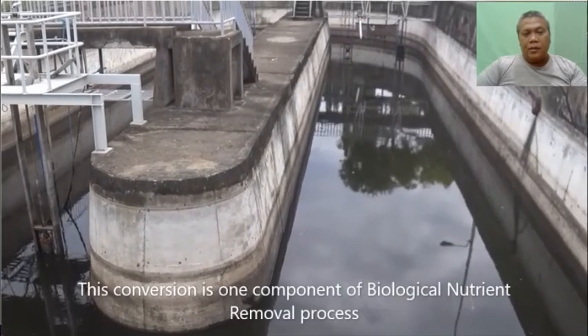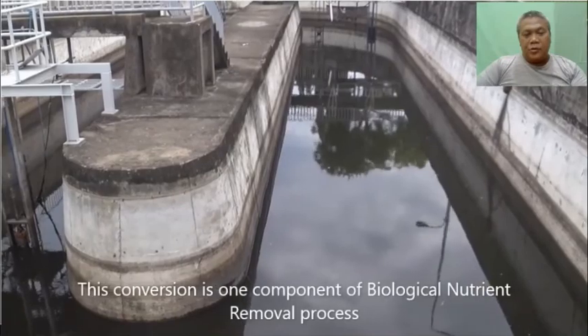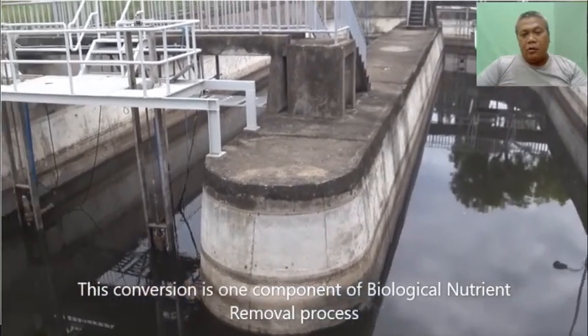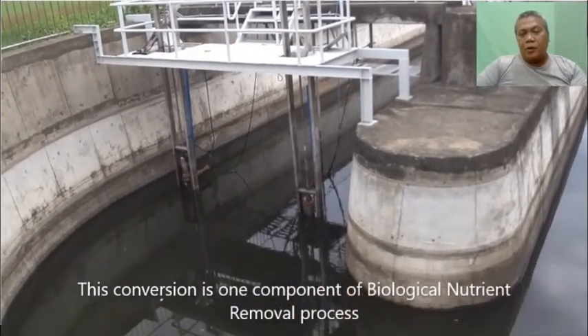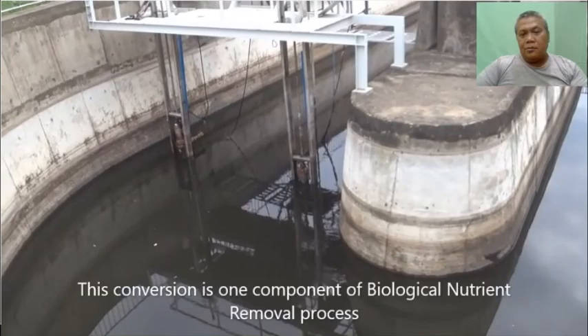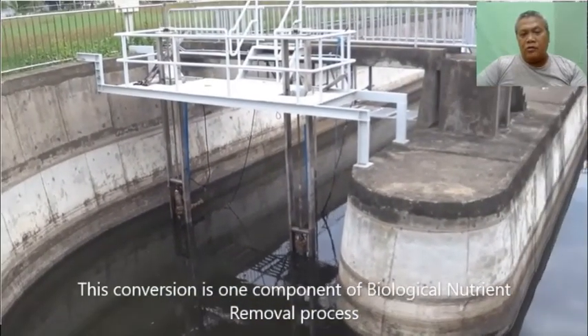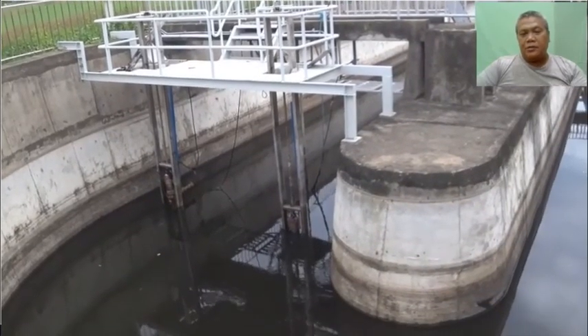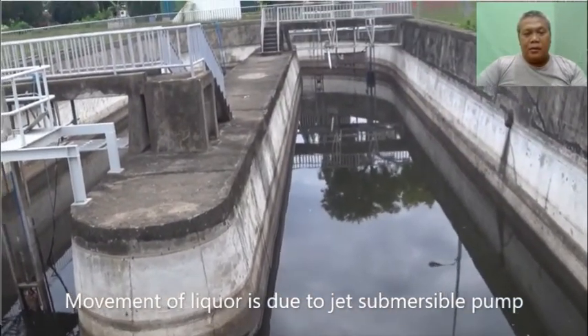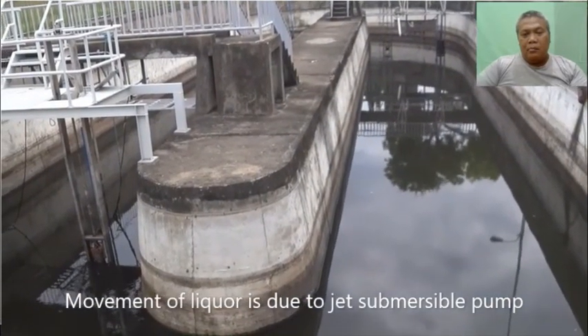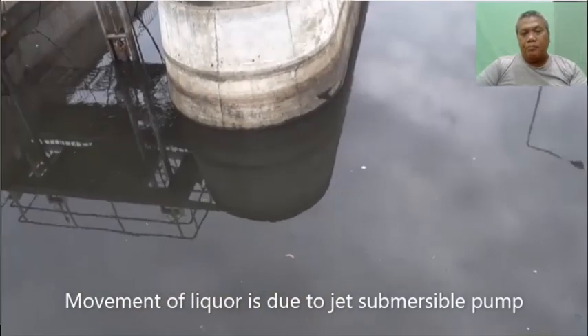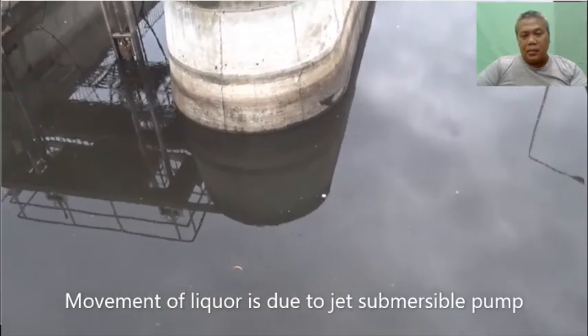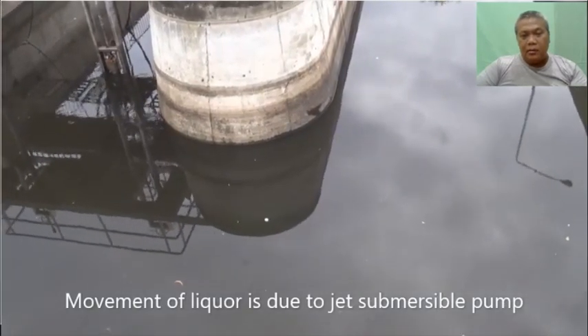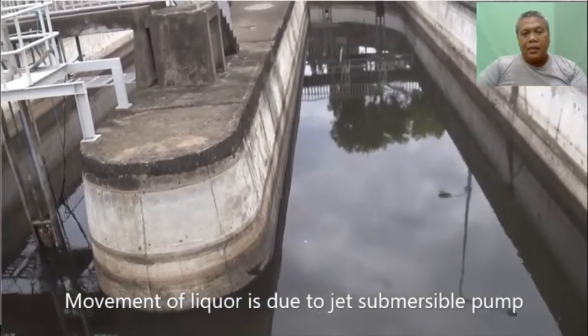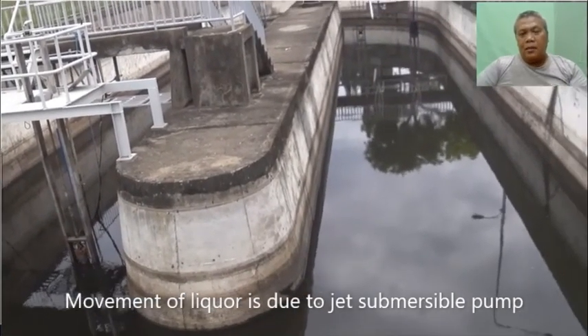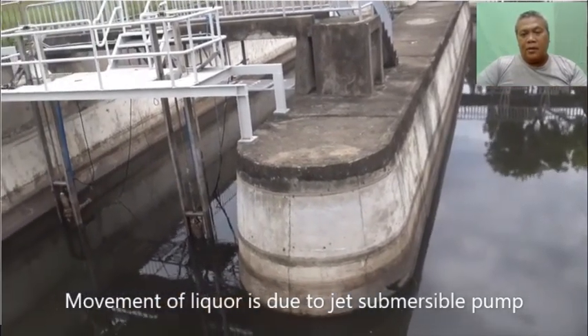Those are the jet pumps that we are using to make it happen. So this is one of the components of the biological nutrient removal process wherein we converted the oxidation ditch from an aerobic process into an anaerobic process. Before, we used to have a problem with FOG. Now FOG can just come in because it will be handled by this anaerobic process, and it will be moved around by a jet pump. It is moving slowly. You can see the movement of the liquor, and although it has no cover, it is anaerobic. Maybe there is oxygen at the surface, but it cannot penetrate.